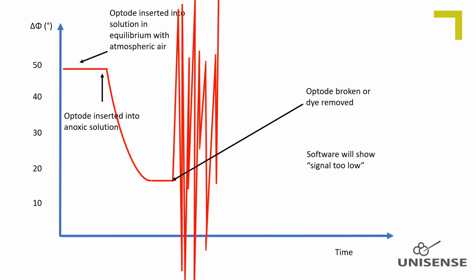A signal too low prompt could be due to a broken tip, but it could also be due to a broken fiber, which will give the same symptoms. The glass fiber does not tolerate sharp bends, so please be careful when handling the glass fiber. It is not possible to repair a broken Optode.